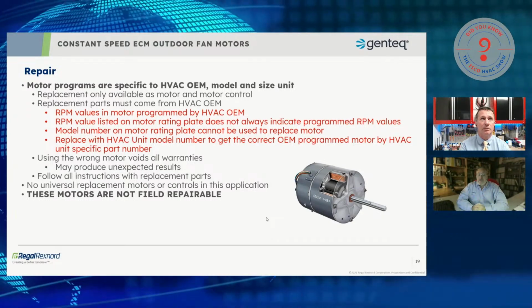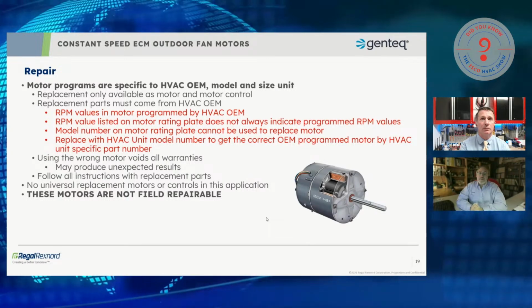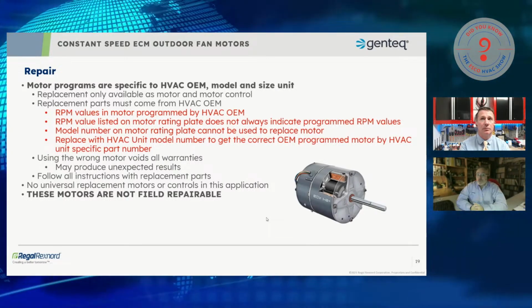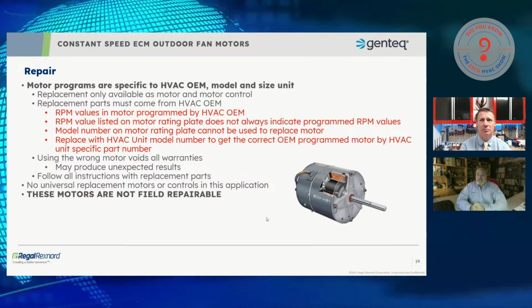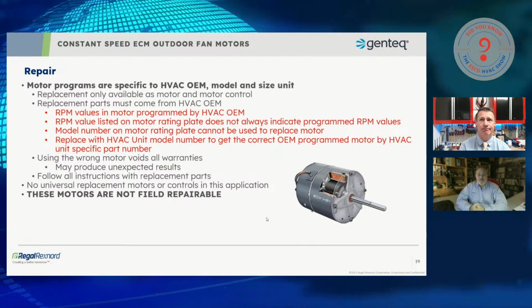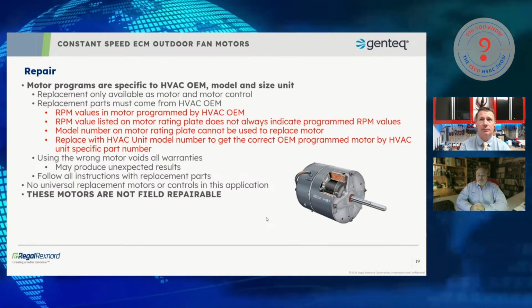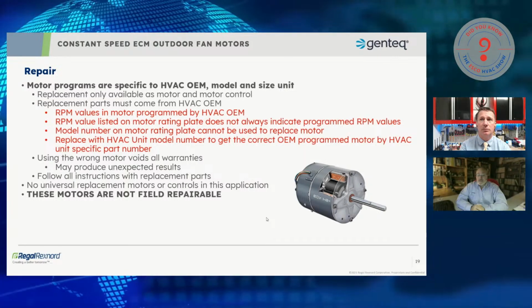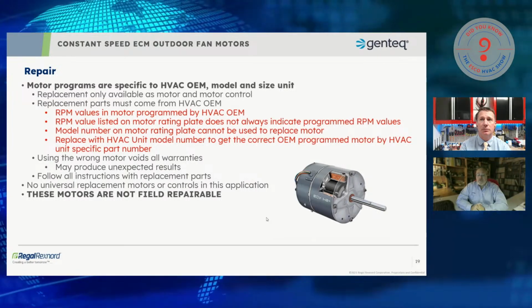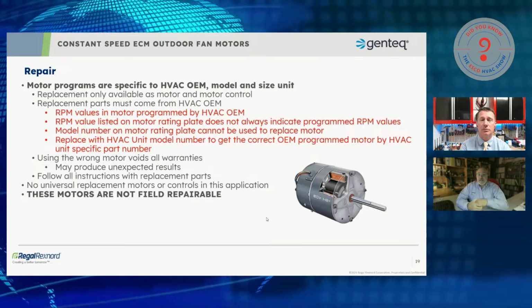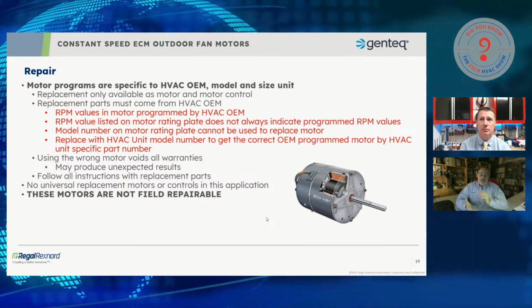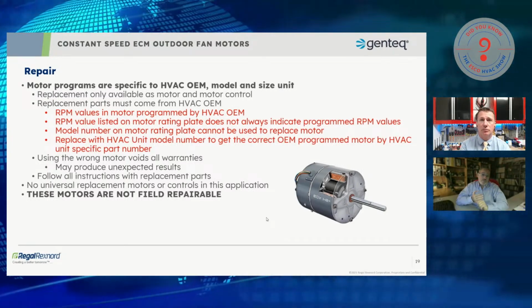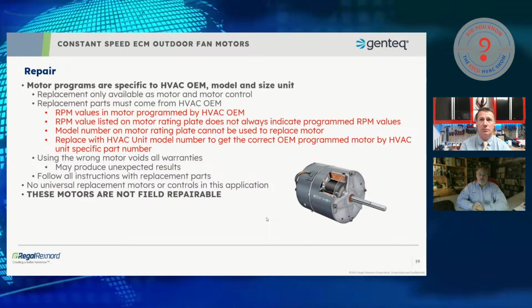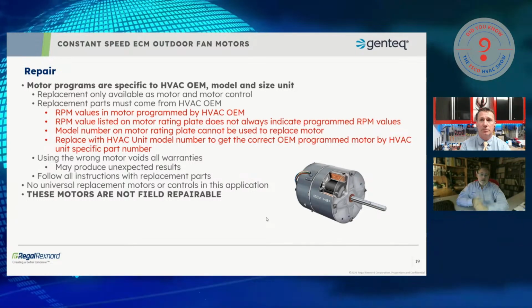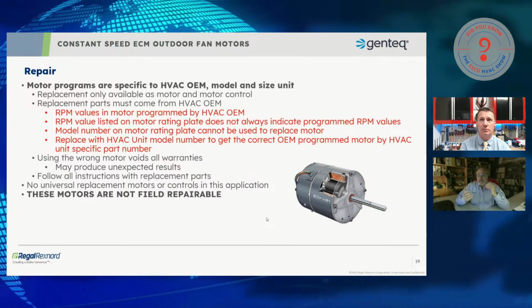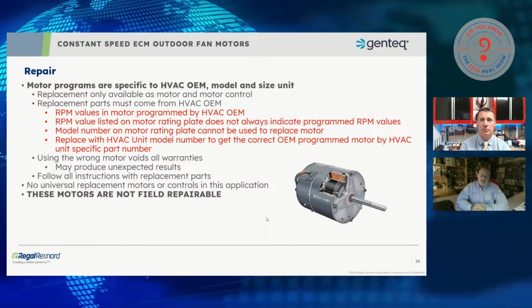I have been getting reports that technicians are replacing these with PSC motors when the OEM motor is not available. It's 100 degrees in Dallas. The customer's not going to wait 2 weeks for a motor. If it's not available, technicians are putting in PSC motors. And for that, I'll simply say, be careful of what you're putting in. If you put in the wrong motor, you could affect the efficiency of the appliance, which may or may not be so bad as long as you're still getting cooling, but you could also affect the longevity of the motor if you put in a higher RPM motor than what was there.